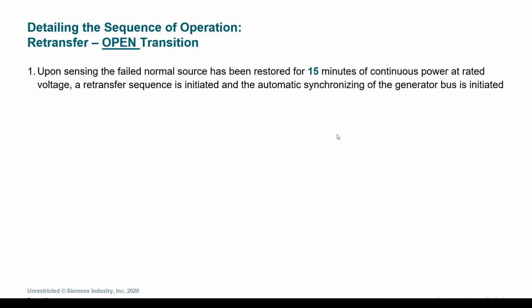Now we'll look at that same sequence of operation in an open transition sequence. In an open transition sequence, we will see that interruption from emergency source to normal source. Although it will only be a brief second, it is worth mentioning that any computer or data loads will be interrupted. So again, in the same sequence, upon sensing that failed normal source being restored for 15 minutes, again, programmable, at that rated voltage, the retransfer sequence is initiated, and this automatic synchronizing of the generator bus is initiated.